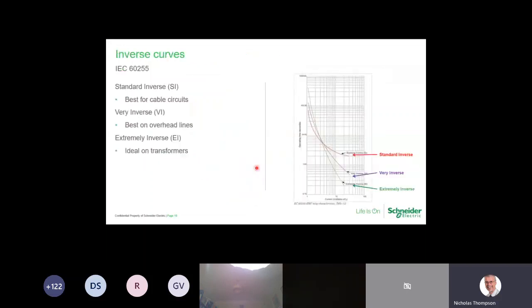And these are just 3 examples of the classic curves which we would see here in the UK. Other countries will have different curves. It depends on the practice for that particular country. These are IEC curves. The Americans have a different set of curves, the ANSI NEMA. And these are the kind of recommendations given in IEC for where the different kinds of curves are going to be used. So if we look at the extremely inverse curve there, it says ideal for transformers.